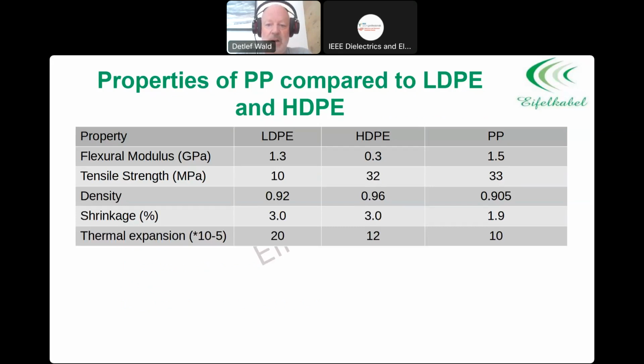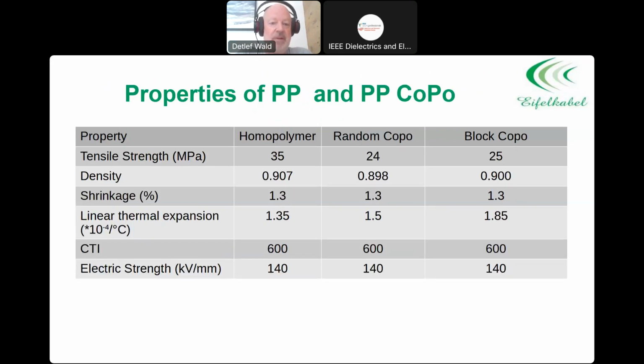Polypropylene is more stiff than LDPE, but more flexible than high density polyethylene. The tensile strength is higher, the density is lower, the shrinkage is also lower, and the thermal expansion is also lower. So you have less expansion when you heat up the cable or shrinking down. The lower density gives you, I would say, a minimized advantage because you need a little bit less material when you extrude the cable.